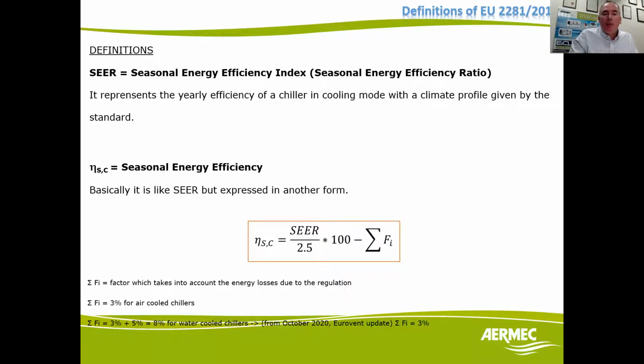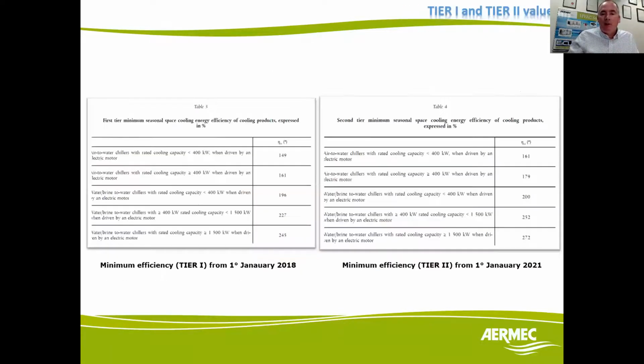The NSC, by the way, is another variation of an efficiency formula, as you can see here. But basically, the point being, you need to be achieving these new levels of efficiency to meet Tier 2. So this is just a sample to give you an idea. For example, under 400 kilowatts of your air-cooled water chiller, you would have needed an NSC value of 149 or higher. Now you must achieve 161 or higher.